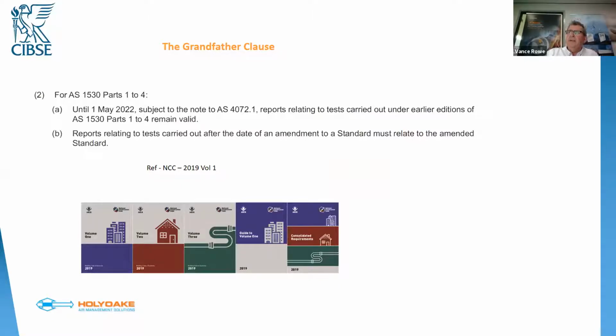Quickly covering the grandfather clause. The grandfather clause exists in the NCC, and it states until May 2022, subject to the note to AS4072.1, reports relating to tests carried out under earlier editions of AS 1530 parts 1 to 4 remain valid. Excuse me. Sorry. Right. It is quite interesting to understand that if we manufactured or developed a new fire damper, we couldn't refer to that clause. We'd have to test that new fire damper to the current standard. The grandfather clause also only exists for fire dampers. It does not exist for smoke dampers.